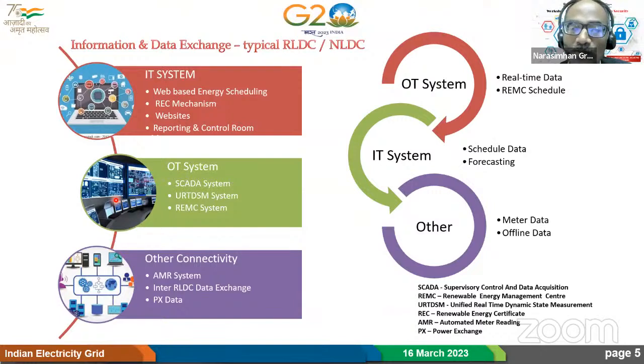The AGC is a very slow type of control. Signals are sent every 4 seconds to the power plant, and finally it lands in the power plant's distributed control system. There again, the ramp rate, everything is checked. You can't have a situation where the AGC tells the plant to double the generation instantaneously. It won't happen - it's a slow control, a proportional integral control. So as far as grid security is concerned, it's not going to impact the security of the grid.